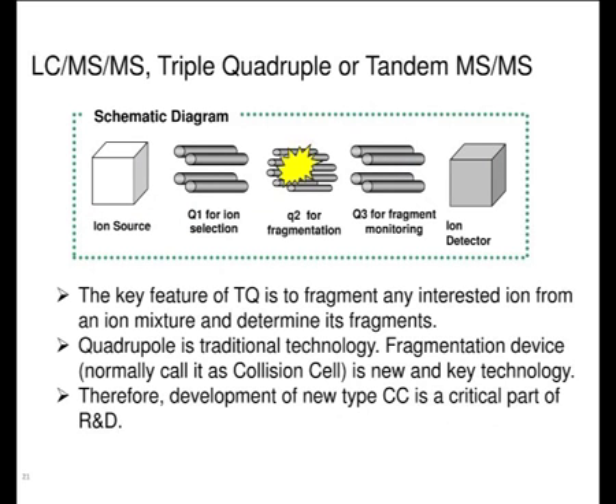In the triple quadrupole, how does it work? It contains three quadrupoles, Q1, Q2 and Q3. Mass filtration of the ions takes place in Q1 and Q3. The second quadrupole is used only for fragmentation. Here we can select a particular ion of interest in the first quadrupole. It passes to the second quadrupole, which contains some collision gas, known as argon or nitrogen.